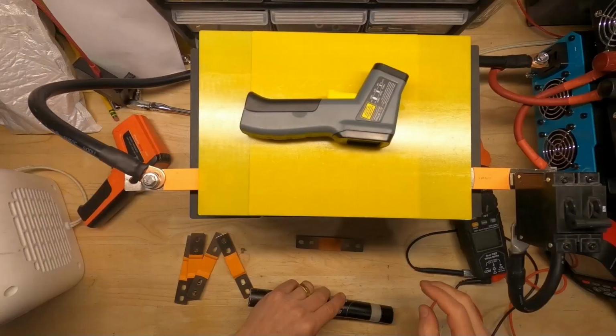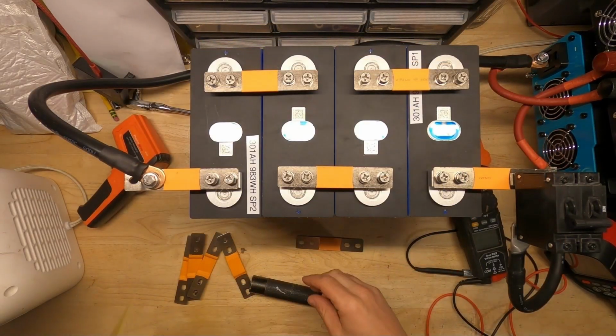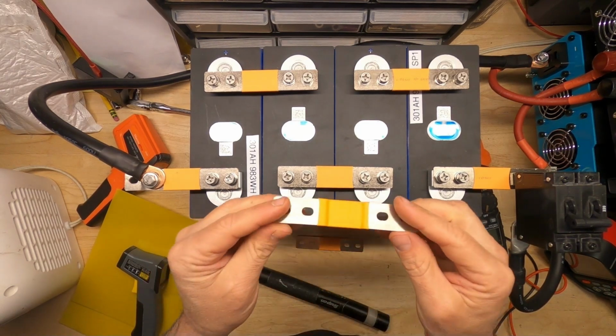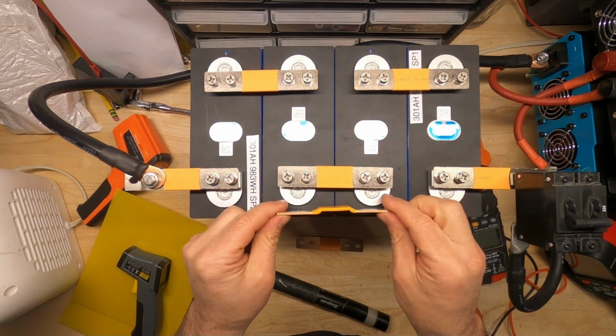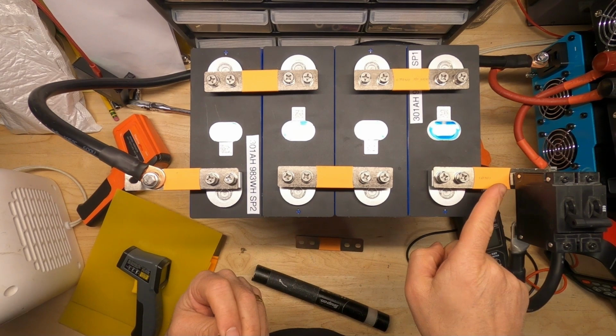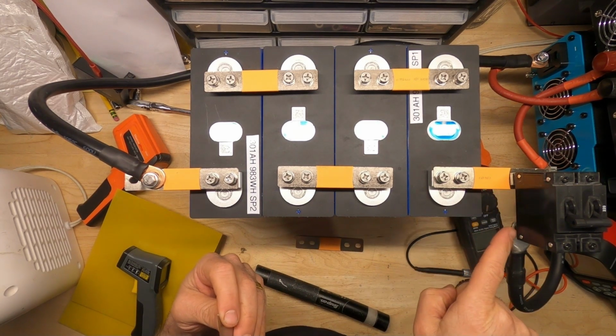As far as I know, they do not ship the aluminum rigid bus bars anymore, but if you end up getting both, make sure you use the copper only. We're going to rebuild this battery pack using the flexible copper bus bars, and we're going to take these metal bridge pieces out of the breaker.